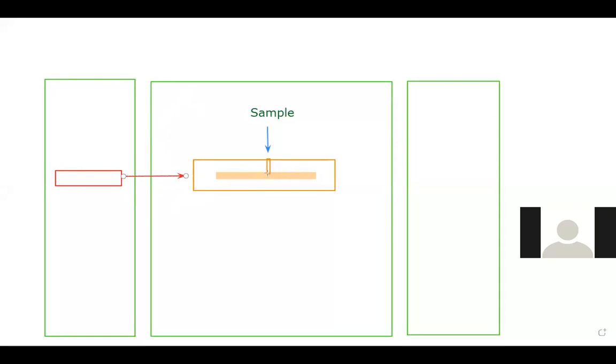Okay, the sample goes inside, and then this is heated at a temperature of say more than 3000 degrees centigrade. That is why the sample will be instantly vaporized, and you see that the volume here is very, very small, and therefore a large number of pure atoms will be generated because of the rapid, very high degree heating.